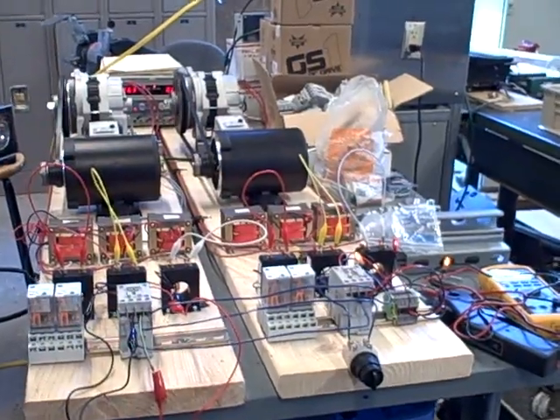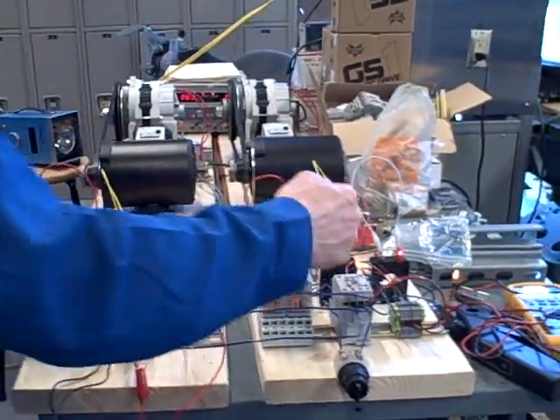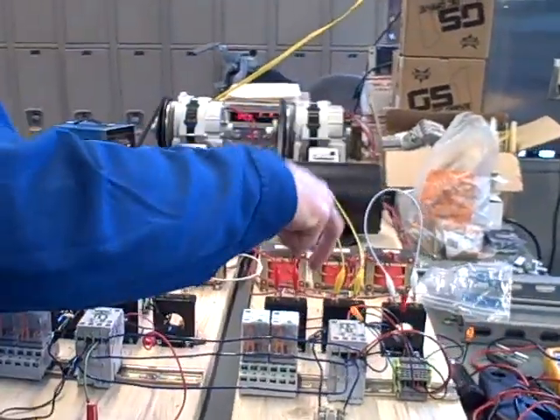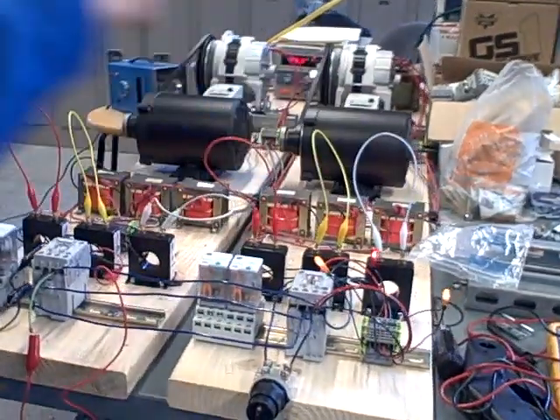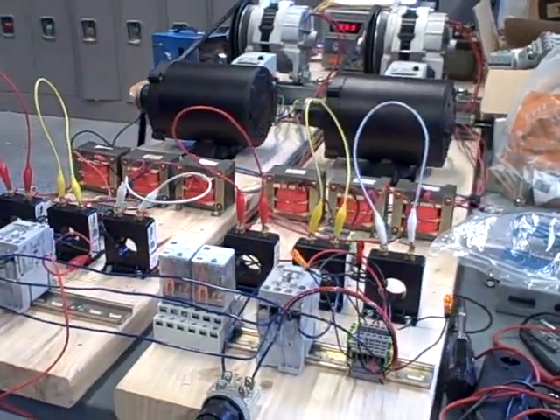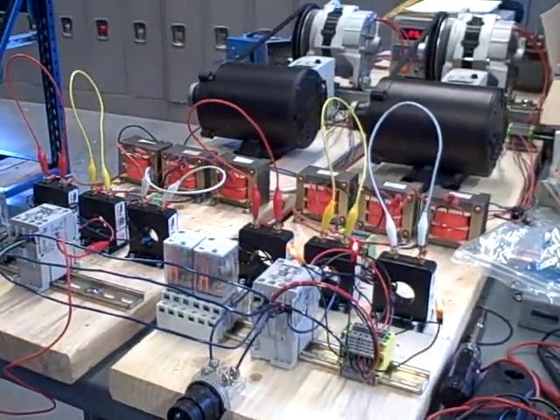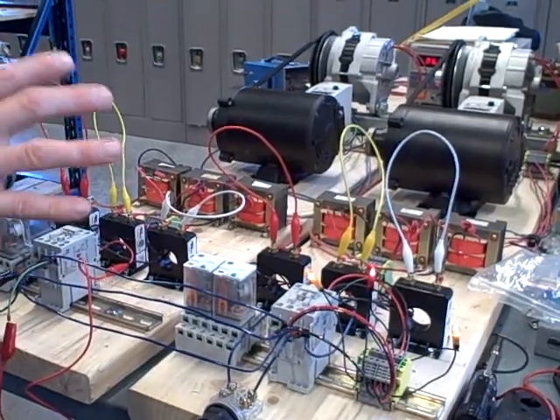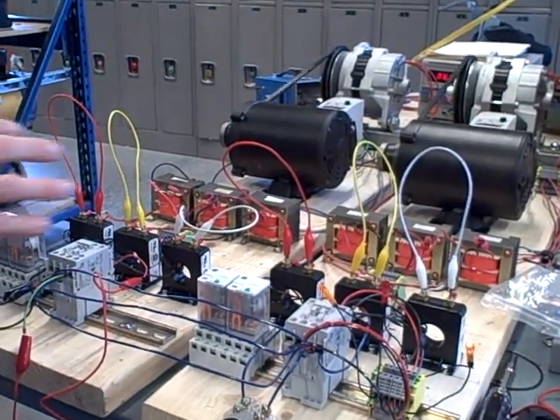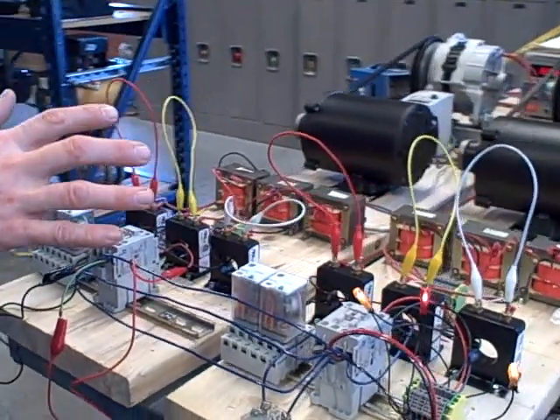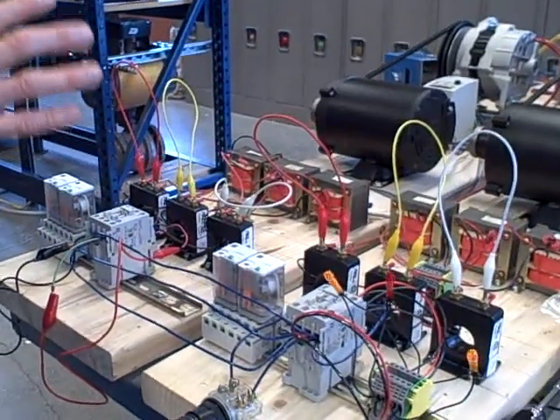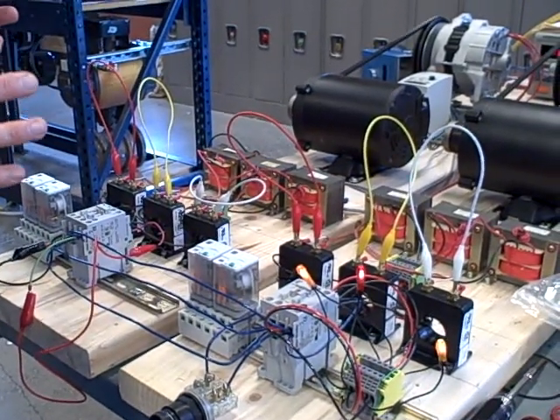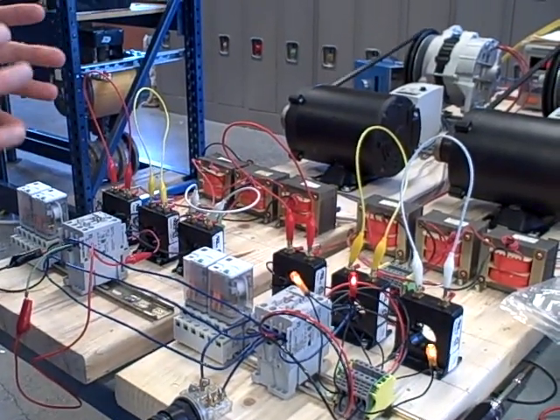That circuit breaker is currently open, and we have three neon light bulbs connected across the poles of each circuit breaker contact. Now, you'll see these light bulbs are blinking. What that's telling us is that these two generators are not in phase with each other. They're both putting out three-phase power, about the same voltage, but one's going a little bit slower than the other one is. And because one's going slower than the other, they're continually falling in and out of sync with each other.